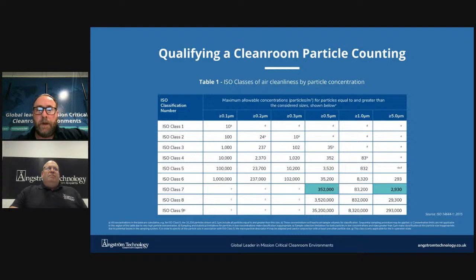For example, an ISO class 7 cleanroom must have less than 352,000 particles at 0.5 micron and less than 2,930 particles at 5 micron in each location sampled. The average count for the room may pass, but should any one location exceed the allowable concentration, that will cause the room to fail.